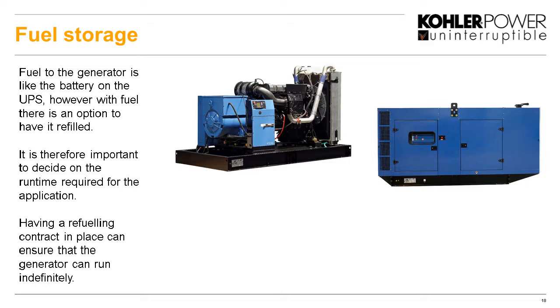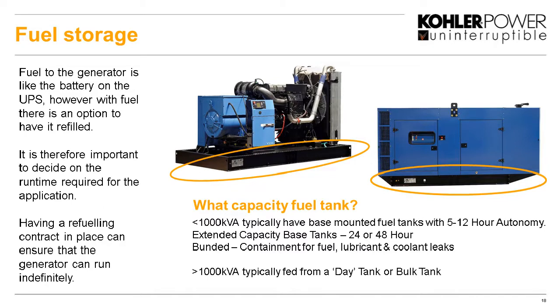Obviously that's very critical, that we have a contract in place so that we can get the fuel in the required time, but it's an option that needs to be considered when we're looking at the actual fuel storage that we need. Okay, so like I said from the beginning, typical fuel tanks are bolted into the bottom. Now, less than 1 MVA, we typically have, depending on the set and the tank, sort of 5 to 12 hour run times. We can have extended base tanks that can run for longer, maybe a day or two. When we want bigger than that, we have to have separate fuel tanks, and typically on large generators, we would have to have a separate day tank or bulk tank as well for that to run anyway.